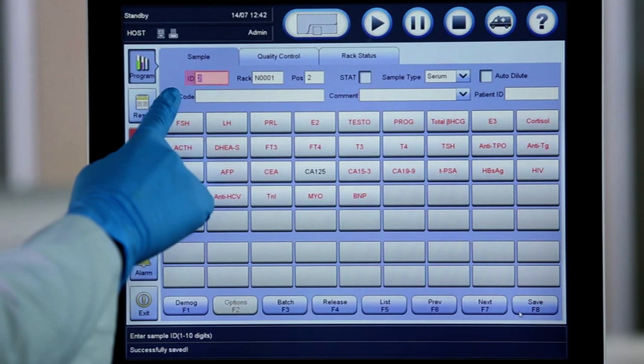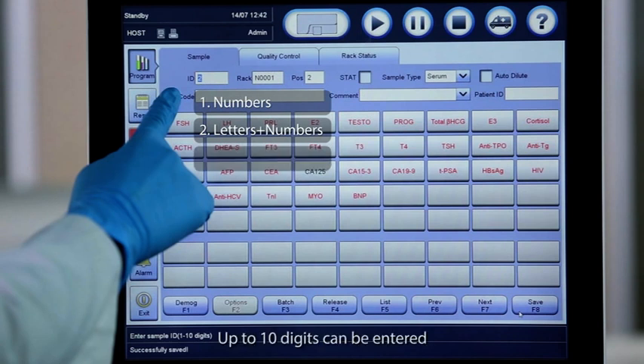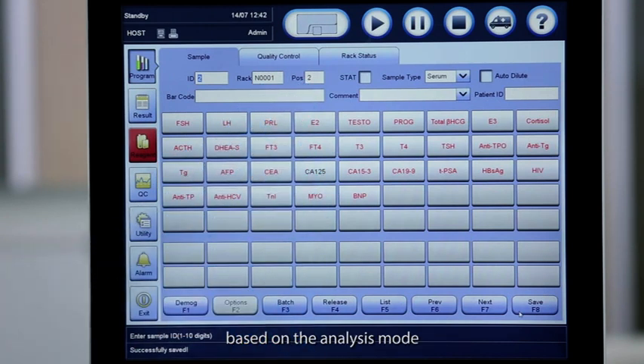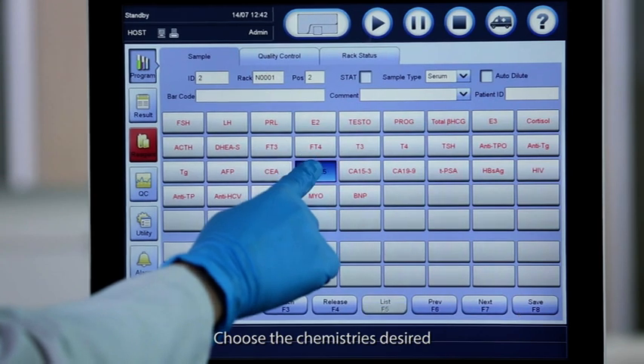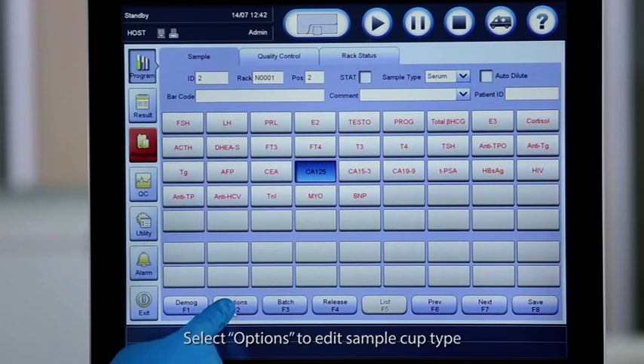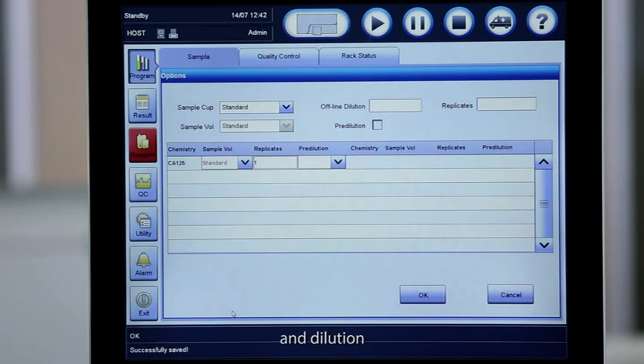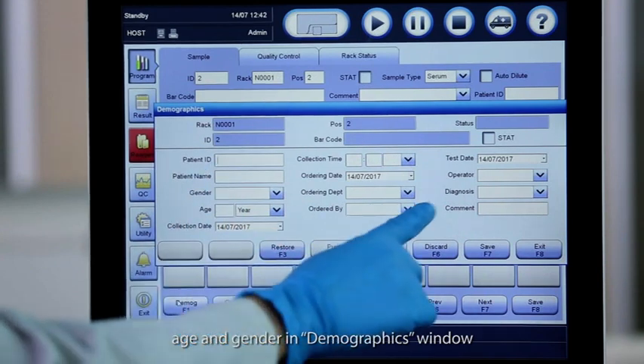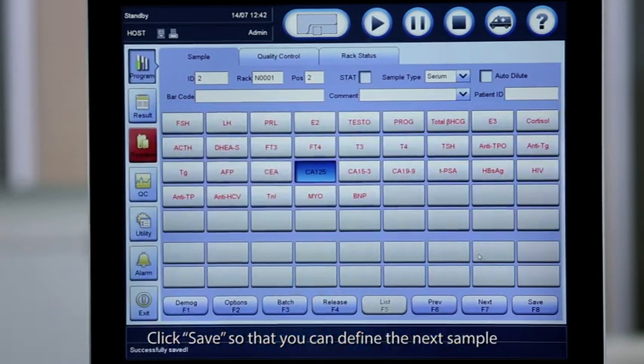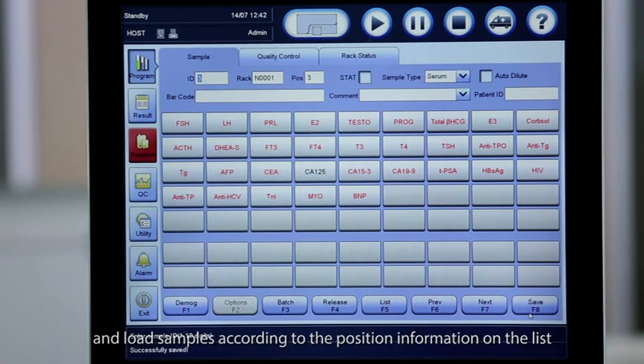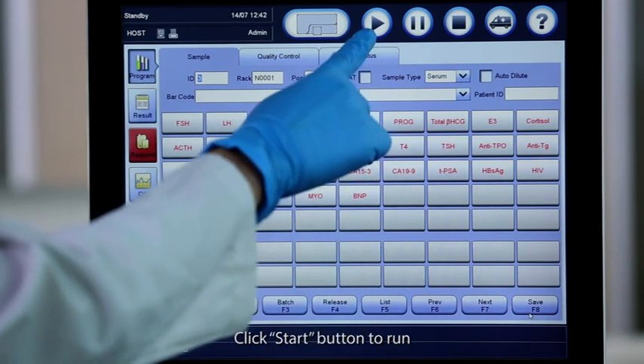Enter the sample ID. Sample ID is composed of numbers or letters and numbers. Up to 10 digits can be entered. Input the Rack ID and position number based on the analysis mode. Choose the chemistries desired. Only those in black can be requested for analysis. Select Options to edit sample cup type, replication and dilution. Edit patient information such as age and gender in Demographics window. Click Save so that you can define the next sample. Click List and load samples according to the position information on the list. Click Start button to run.